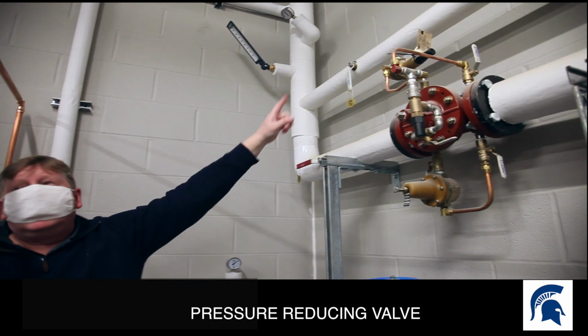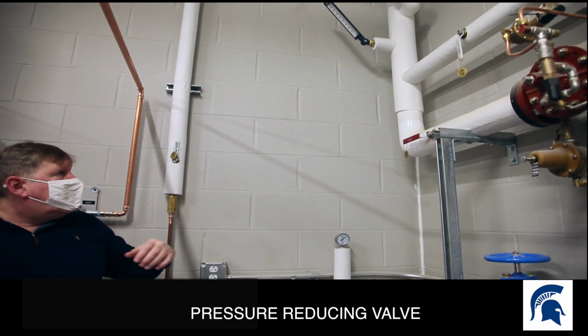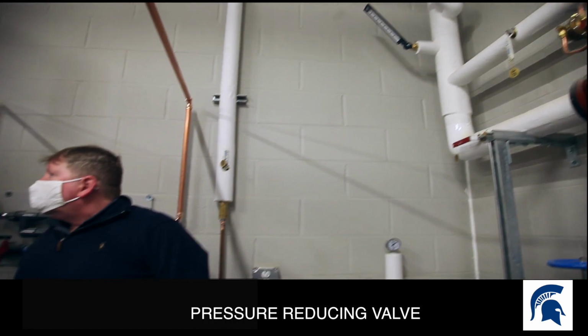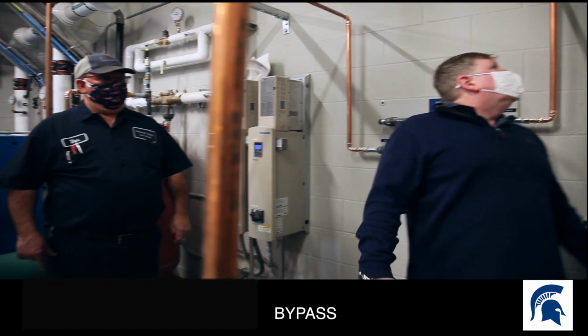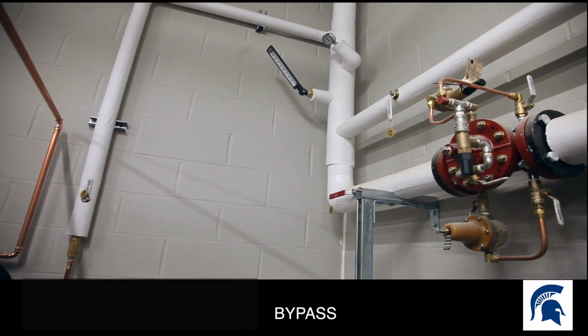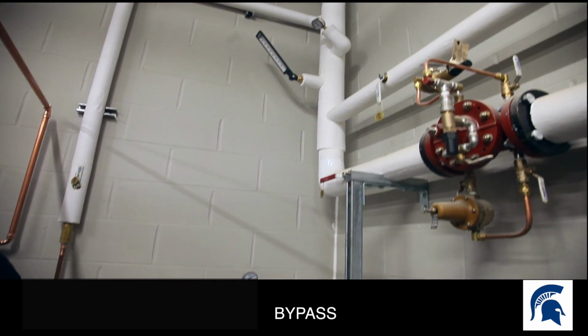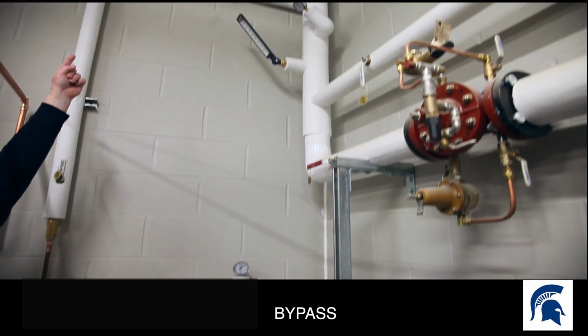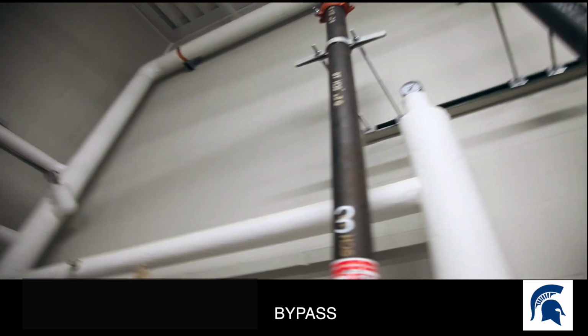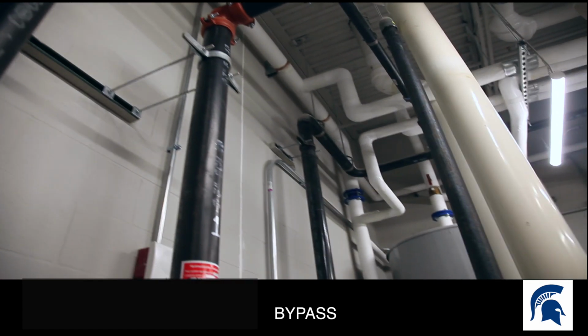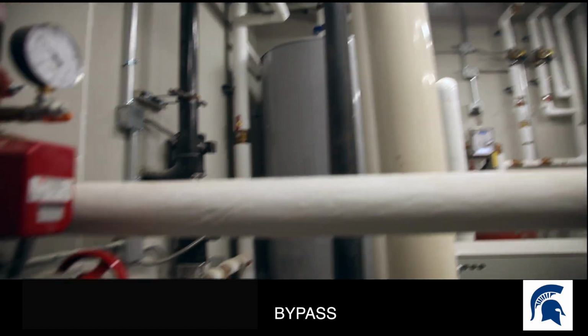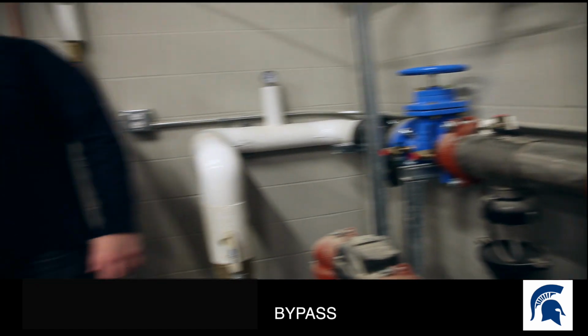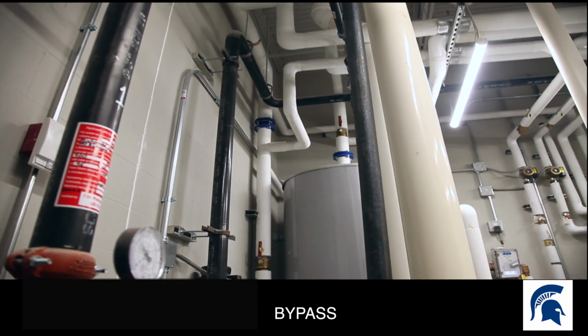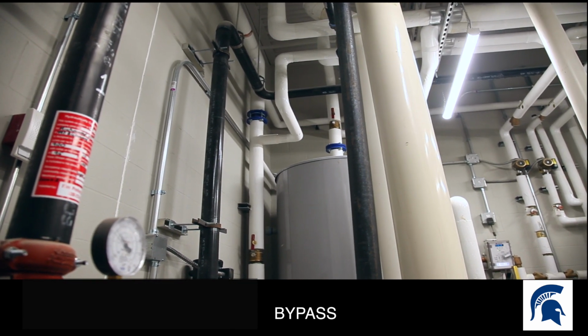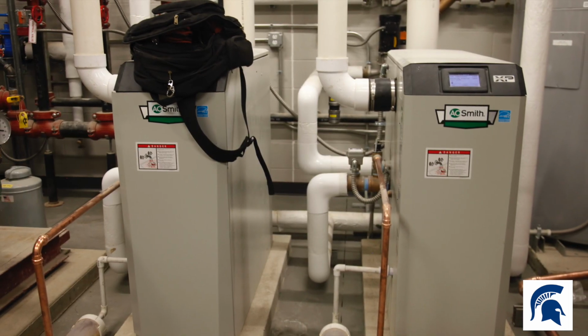This is your bypass. That's the inlet water temperature coming from the street? Yeah. That's not hot water. Correct. It's the water temperature from the street, you're at 55 degrees. Backflow preventer. So the main water, then the cold water goes up, and the feed branches off and feeds the rest of the water. Over, comes down, goes over here, you see that check valve there, the blue check valve? Yeah. So I believe that's your feed to your water heater, so you don't get hot water back.